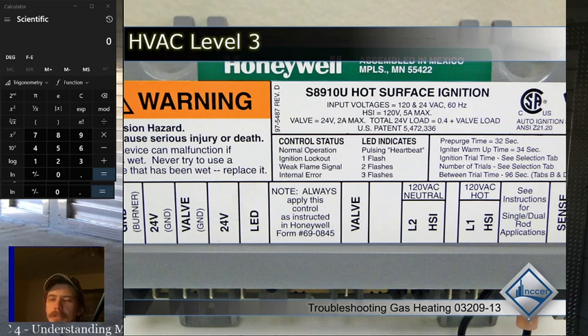And then the last question on your test is about different durations of defrost mode. So remember, I told you after 30 to 90 minutes you're going to enter defrost mode because of time. Okay, so you don't want a system, especially when it's very cold outside. If you just let defrost happen anytime that the defrost thermostat says the coil is cold, then you could be going into defrost like every 5 minutes.